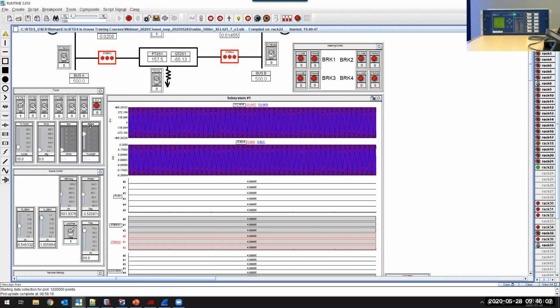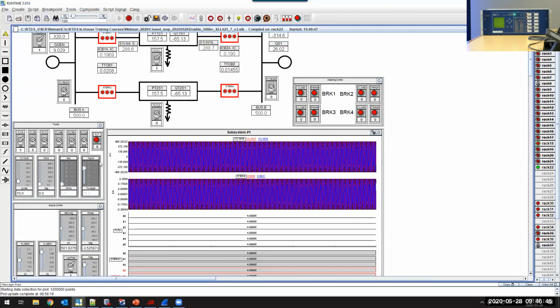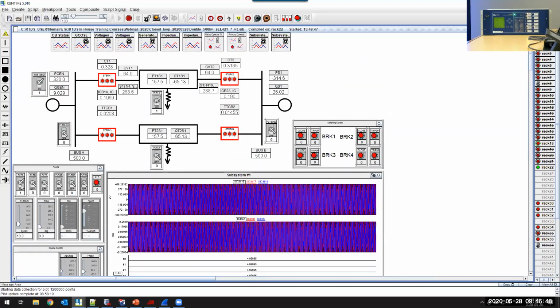For now, the drop variable slider is set to 75%, which means the fault location is at 75% of the original length from the left terminal. Since the relay is at the right side terminal, the fault location is at 25% of the original length from the relay side, which, considering the length is 97 kilometers, should be at 24.25 kilometers. And we're about to apply, say, an A phase to ground fault.